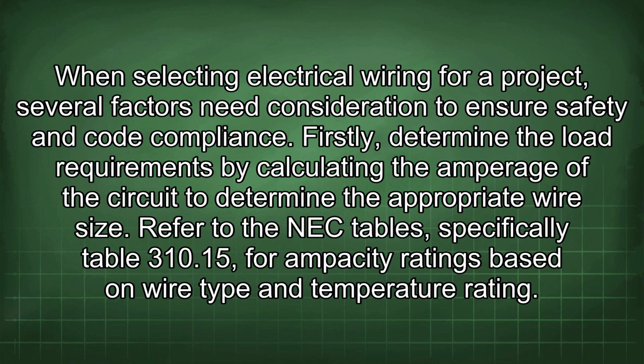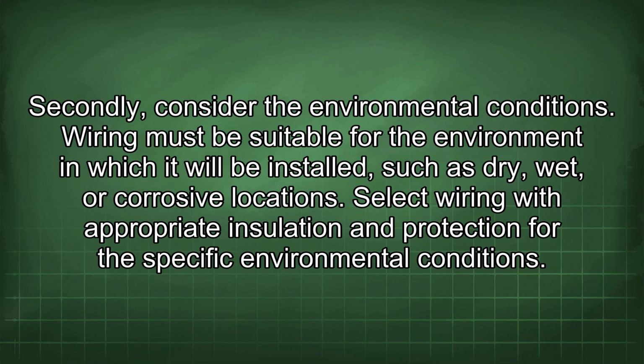Firstly, determine the load requirements by calculating the amperage of the circuit to determine the appropriate wire size. Refer to the NEC tables, specifically Table 310.15, for ampacity ratings based on wire type and temperature rating. Secondly, consider the environmental conditions. Wiring must be suitable for the environment in which it will be installed, such as dry, wet, or corrosive locations. Select wiring with appropriate insulation and protection for the specific environmental conditions.